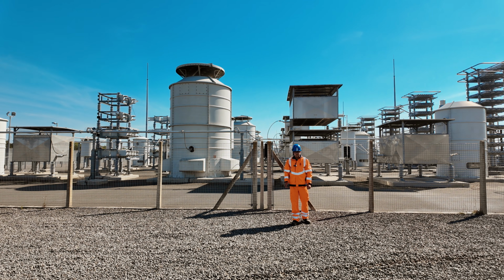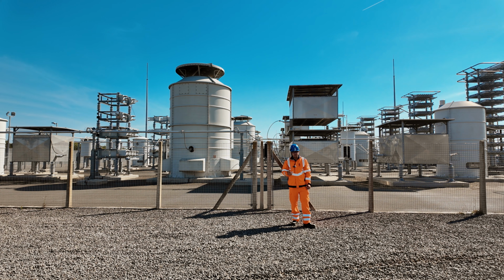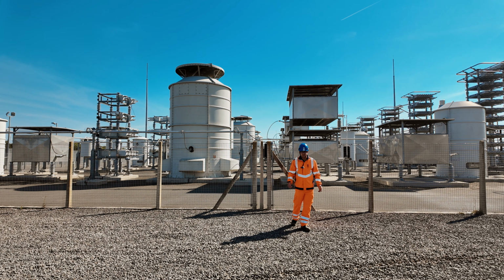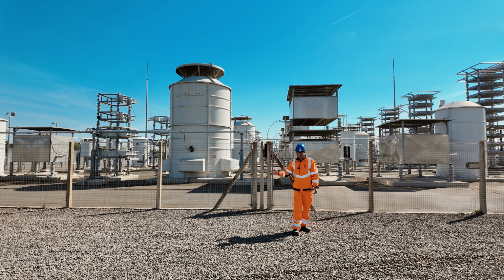Besides the voltage, that enormous air-cored reactor produces a strong alternating magnetic field. If I put a massive continuous conductive loop around it, that magnetic field can induce a voltage around the loop and drive a circulating current through it. Essentially, we've accidentally created a very strange transformer. So conductive structures around the large air-cored reactor have to be carefully designed to avoid closed loops.